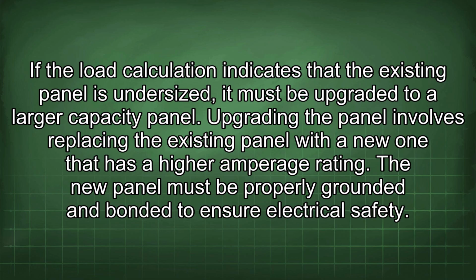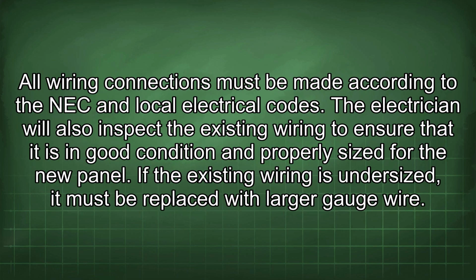If the load calculation indicates that the existing panel is undersized, it must be upgraded to a larger capacity panel. Upgrading the panel involves replacing the existing panel with a new one that has a higher amperage rating. The new panel must be properly grounded and bonded to ensure electrical safety. All wiring connections must be made according to the NEC and local electrical codes.